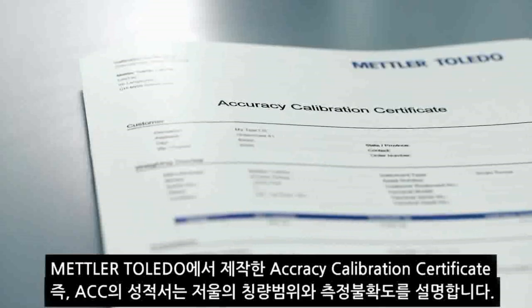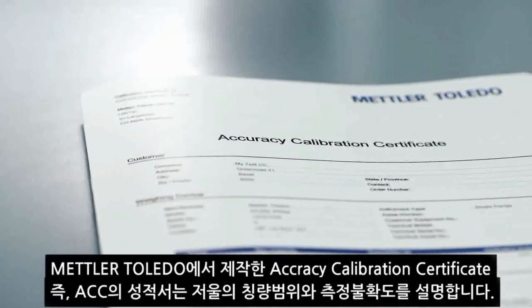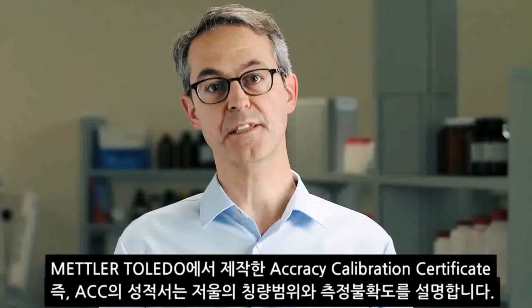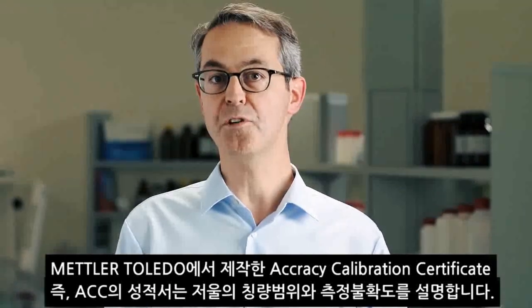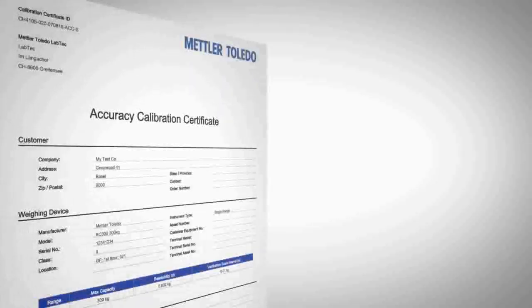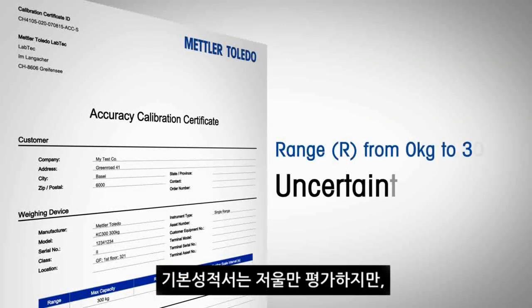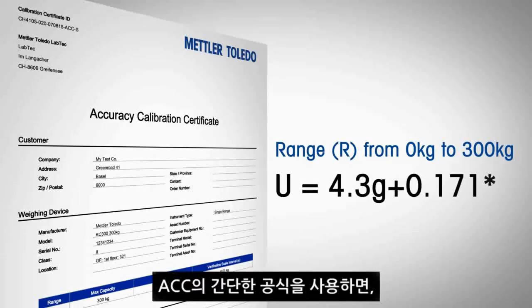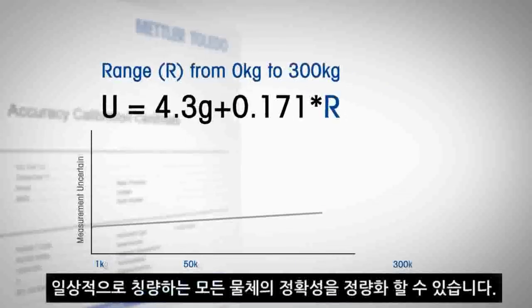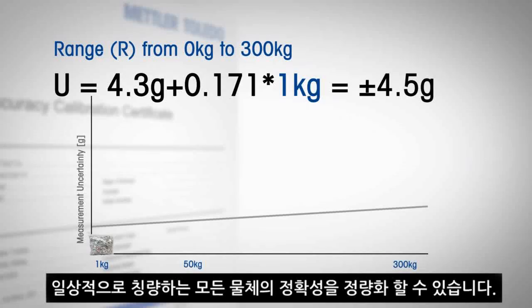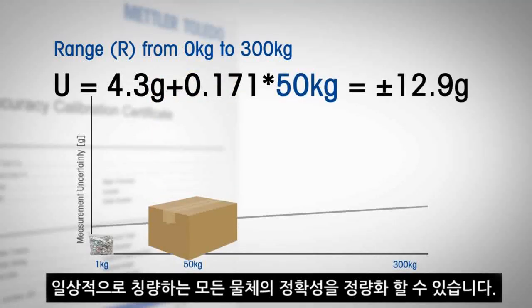The Accuracy Calibration Certificate, the ACC from METTLER TOLEDO, documents this measurement uncertainty over the equipment's weighing range. While basic certificates only assess the equipment, the ACC simple formula allows you to quantify the accuracy of every object you weigh in day-to-day use.